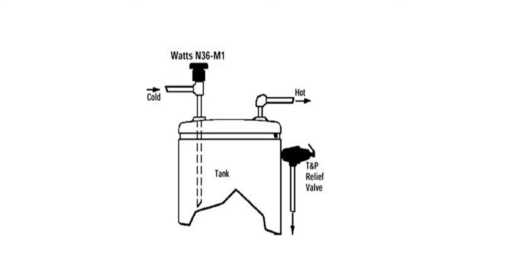The vacuum relief valve is located above the water heater and will open to the atmosphere when a back-siphon or vacuum occurs on the tank. This allows air to enter at the vacuum relief valve so the heater or tank will not be drained down. This protects the heaters from dry-firing the elements or burner and can also prevent the tank from collapsing due to vacuum.